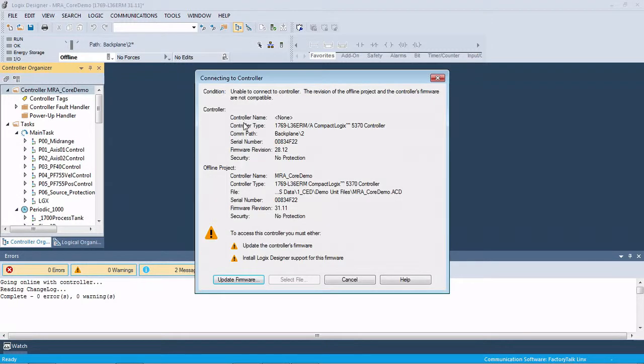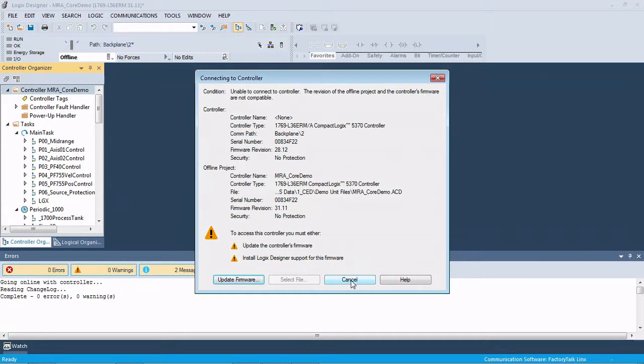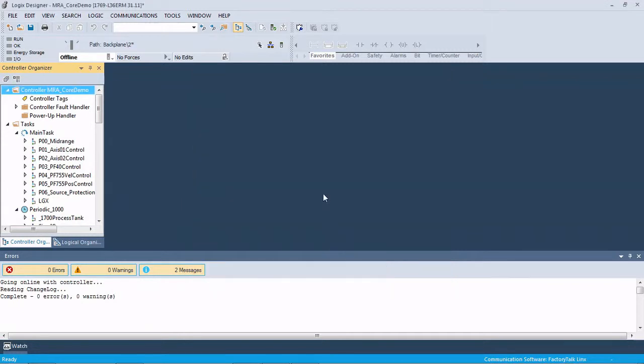Online controller has no program in it, and it's version 28, which completely mismatches our other controller. So now I'm going to go over and I'm going to put our SD card back into our controller and I'm going to cycle power and we'll see what happens.